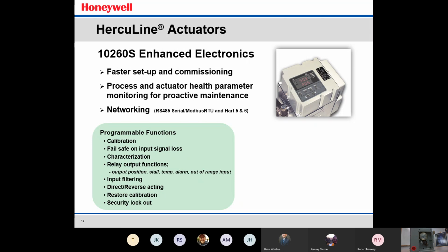Input filtering, so if you have a noisy input, say you have a 4 to 20 milliamp input signal and there's some noise induced on that line going into the actuator, you can set up input filtering to filter out all that noise, allowing you to do very good control then. Direct or reverse acting, you can set up. Restore calibration, so in the event that you lose calibration, you can restore it back to the factory calibration, and it allows a very easy keystroke in order to do that.